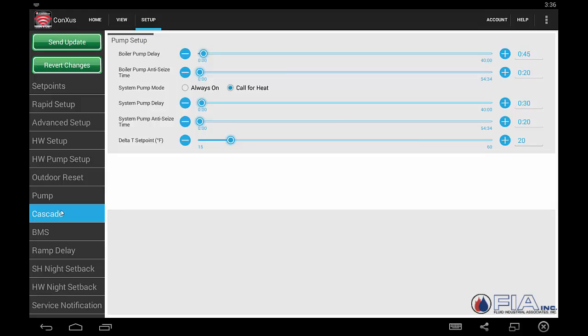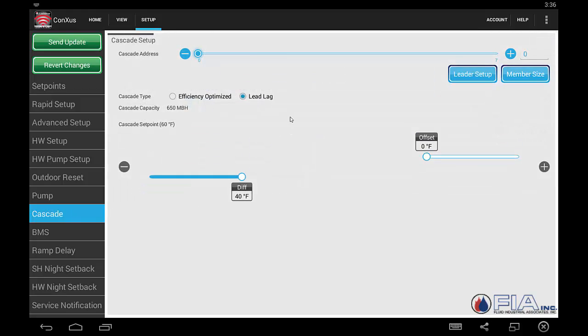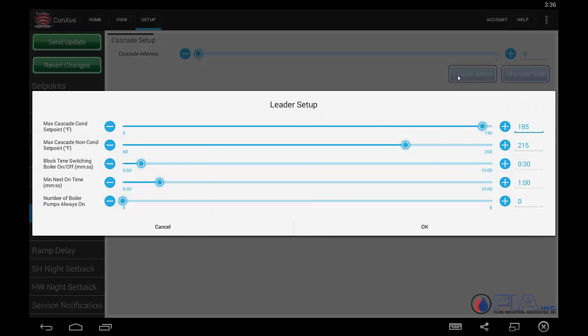Here's setting up our cascade. In this case the address is zero, so it's the leader. Which way do we want it to go? And then in our leader set point, again you see a cascade for condensing and non-condensing. At the bottom, you'll see the number of boiler pumps always on — we can use this with isolation valves in a full-flow system, keeping an isolation valve or perhaps two open to provide constant flow for the system.